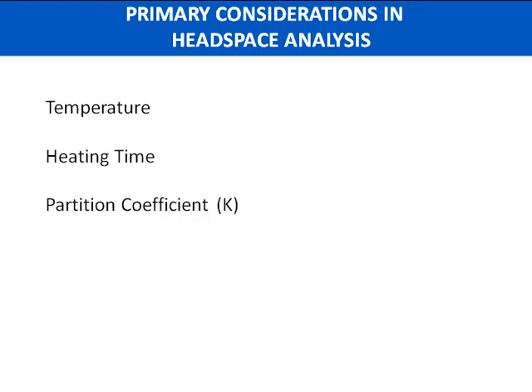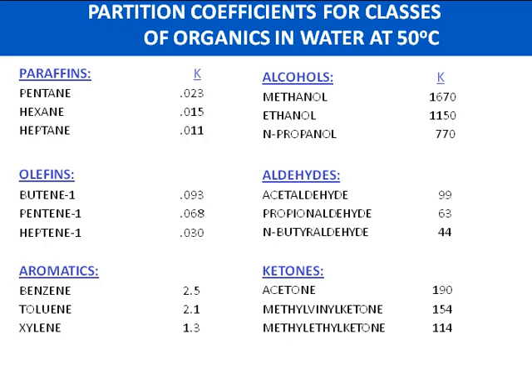The partition coefficient represents the ratio of the concentrations or solubilities of an analyte between the sample matrix and the solvent. Analytes with smaller K values will be least soluble in water — these tend to be your most volatile target analytes. However, they're going to be your most sensitive as well. The partition coefficient has factors that can affect it, including temperature and salinity. This is a good listing of partition coefficients for organics in water at 50 degrees Celsius. Notice that the alcohols, which are very soluble in water, are going to have the largest K values. This table gives you a complete understanding of the K value and the role it plays in headspace analysis.